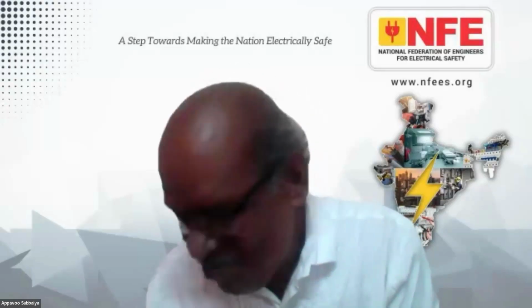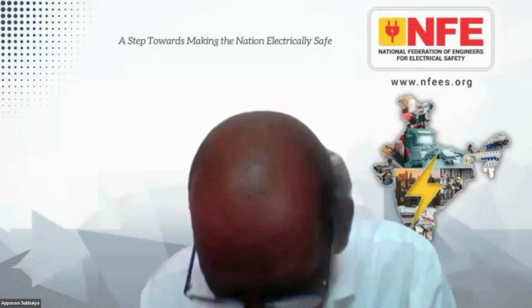Okay, so can I add to this point, sir? Please. Sir, I think Regulation 18 should be read with Regulation 43, sub-regulation subsection 2 and part 2 of that. It has been mentioned clearly that the earthing should be protective multiple earthing, and in addition, the supplier should earth his neutral at the consumer's premises. This is the additional requirement which has been clearly mentioned. Previously it may be earthed, but now it has been made it shall be earthed. So it is additional responsibility on the supplier to earth the neutral at the consumer's premises. If this is really followed, I think most accidents will reduce.